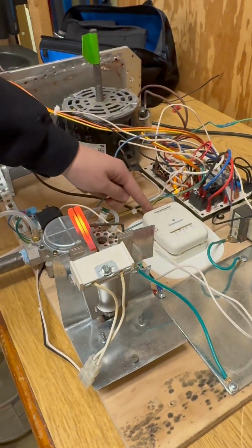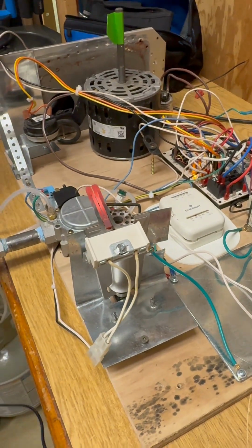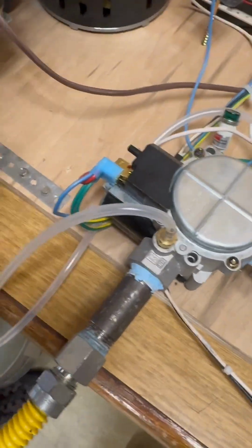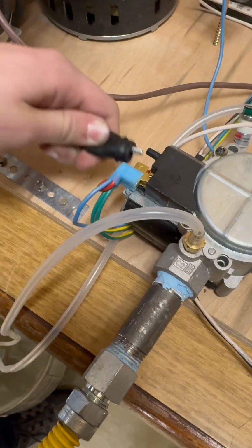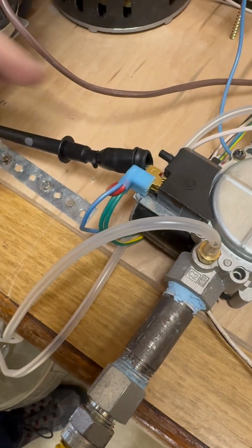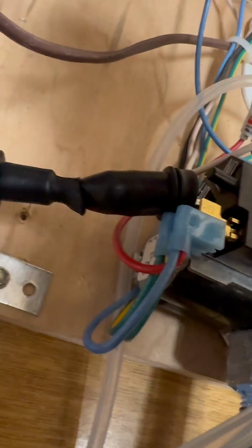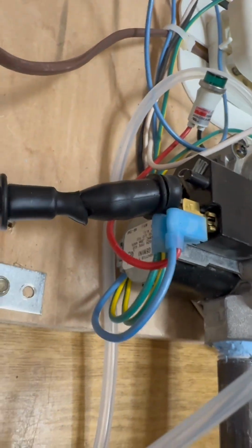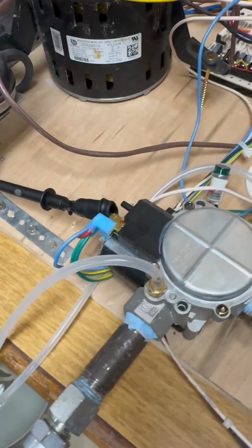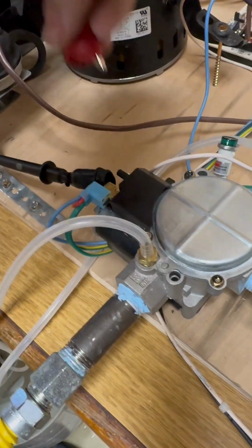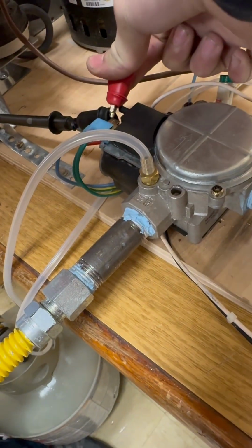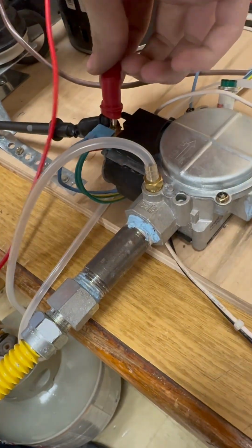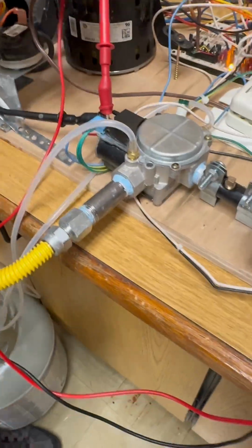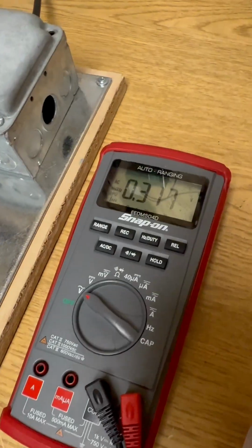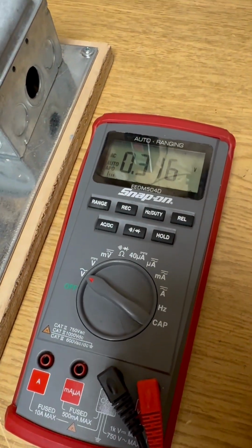So next step is going to be, do we have voltage to our thermostat, or to our gas valve? So I'm going to hook up our meter probes to our neutral and our hot on our gas valve. Alright, so we're going to start our sequence again and wait to see 24 volts to our gas valve.